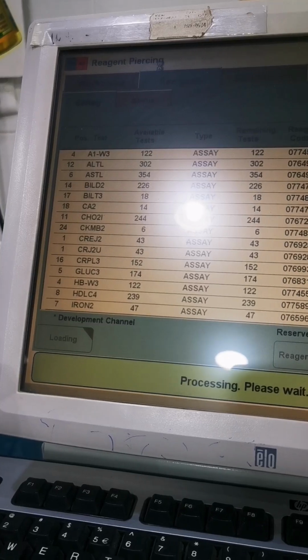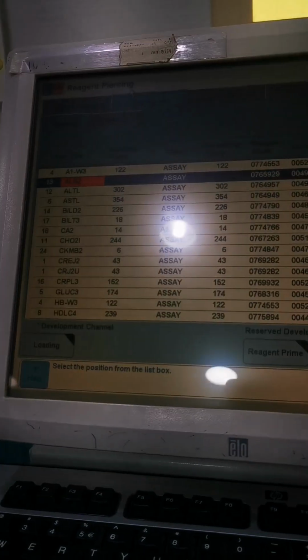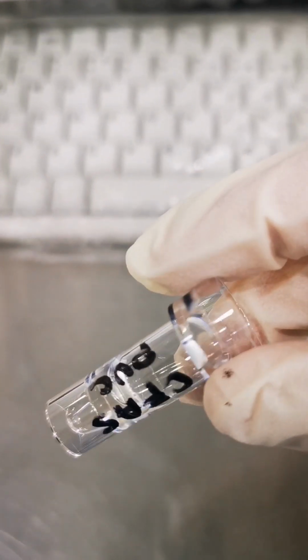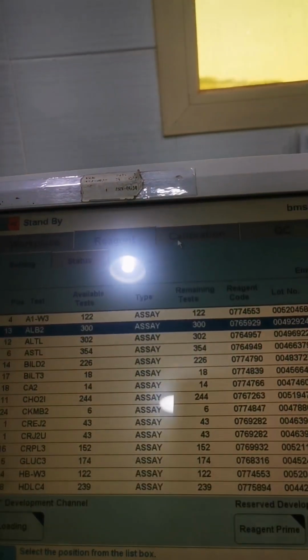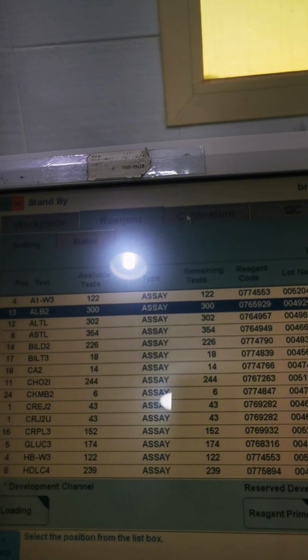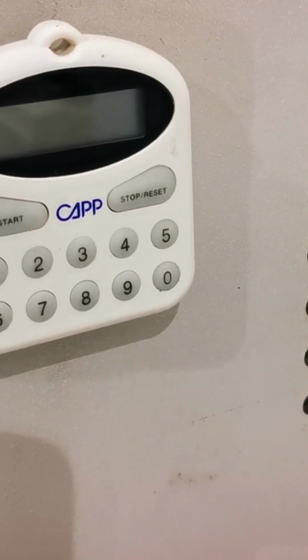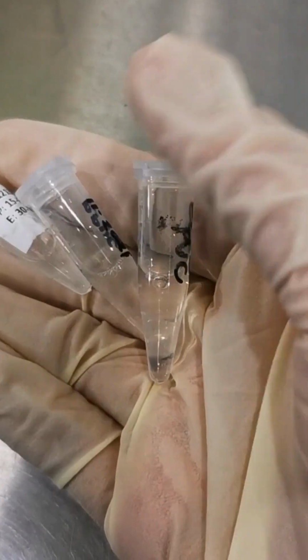Now we need the calibration because every time that we change a reagent into a new one, we need to do the calibration, and after the calibration is okay, we need to run the control, pathologic, normal, and non-pathologic. If normal is not available, we can run the pathologic and non-pathologic control. As we can see, ALB2 has 300 available tests because the reagent is already a new one. Always remember that once we use a new reagent, we must do the calibration and the control first before using that reagent on our patient sample. Before running patient sample, we shall do the control and calibration first.